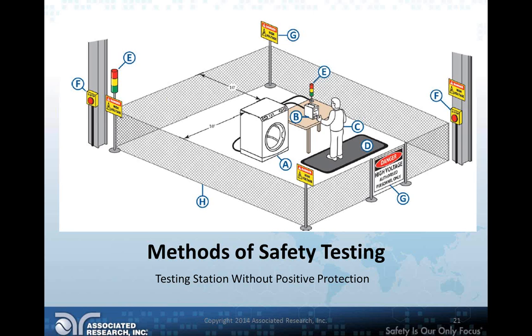Once again, B is our high pot tester, A is our device under test, C is our operator, and then D is another insulation mat. So in this case, we've basically gated off the whole area just to make sure that nobody can come in there and that only the qualified guy labeled C is in there running the tests.